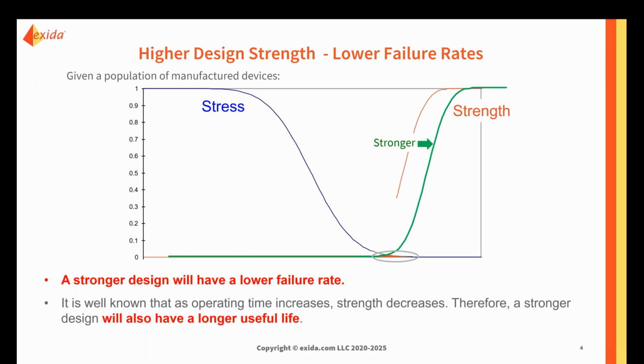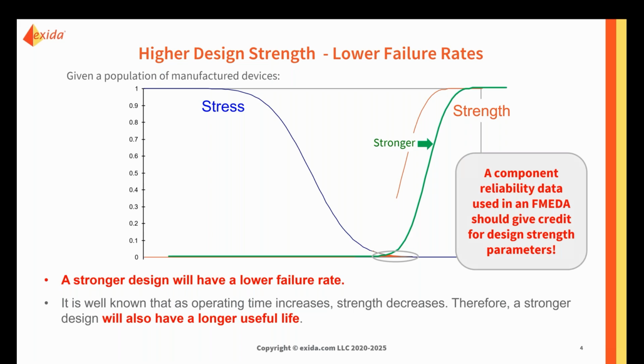Research has shown, based on analysis and operating time, a stronger design will also have a longer useful life. But in order to show that, you have to have a component reliability database that's used in the FMEDA that will give you credit.